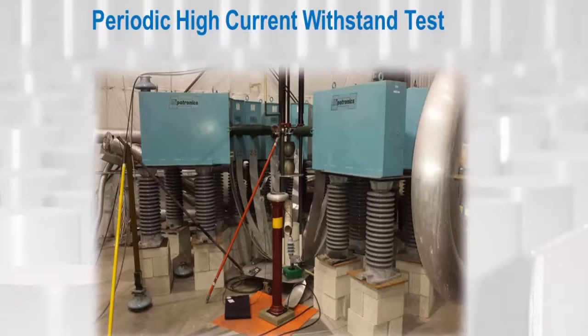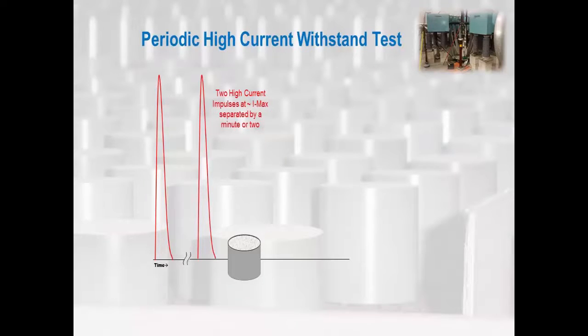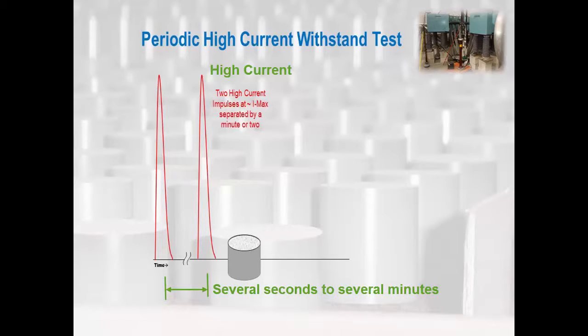One of the most important quality checks of a disc is its high current withstand capability. Yes, I know it is done during the design tests, but it is imperative that it be done periodically on production samples also. This test can predict the performance of an arrestor when subjected to its most onerous duty, high current lightning. For this quality test, the disc is impulsed 1 or 2 times at a very high current. The time between impulses can be a few seconds to as much as a few minutes, depending on the manufacturer.